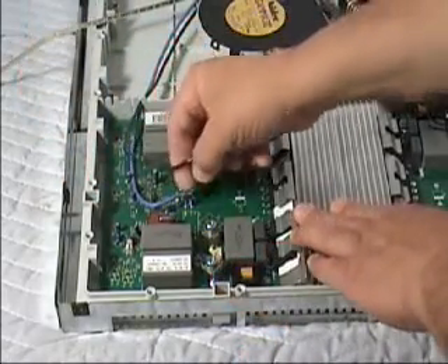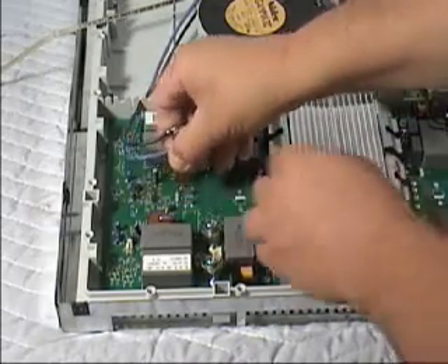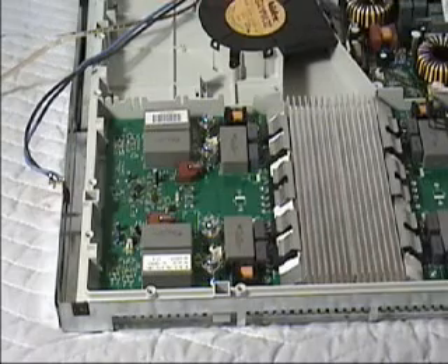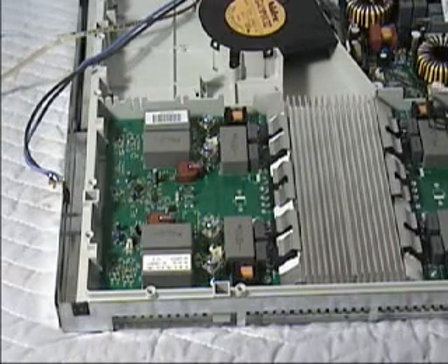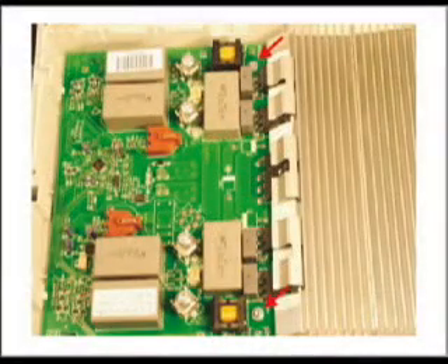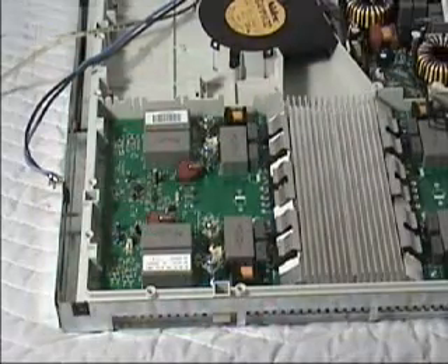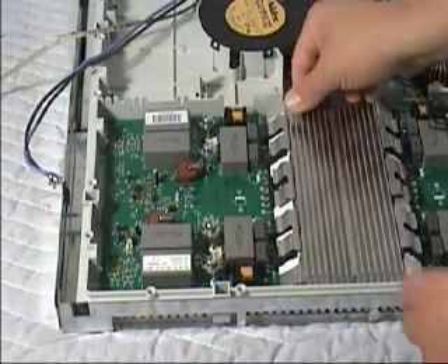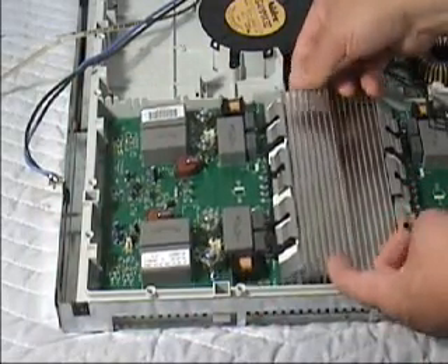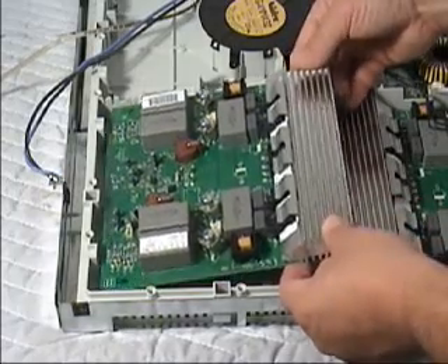Unplug the blue and black wires from the power generator board terminals X1 and X2. When reconnecting these wires, terminal polarity is not important. Remove the 2 Torx screws that mount the board to the outer case. Lift out the induction power generator board.